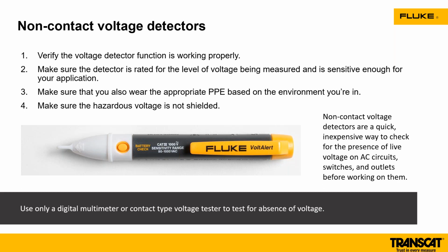For years and years, people would come to me and tell me that these are widow makers, that they don't work right. And I had to explain to them how to properly use them. They're great. They can easily check if you have voltage present on a line. Again, another safety play: if you're working in an environment where you think the voltage is off, even using something like this would help determine if voltage is there or not. This is not a live-dead-live though. Always go back to your meter when making these types of measurements and confirming that.